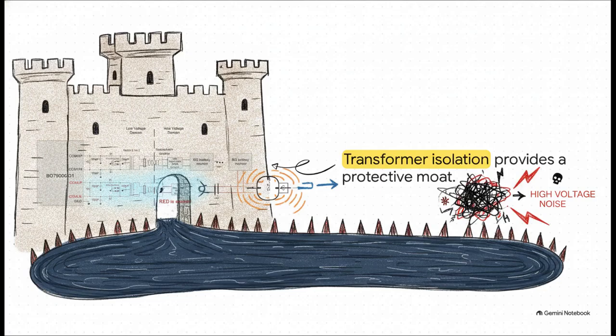To get data across without letting lethal high voltage sneak back in and fry the logic board, we use transformer isolation. These 1-to-1 ratio transformers provide galvanic isolation. That means there's absolutely zero physical electrical connection between the left and right sides. No copper wire connects them.